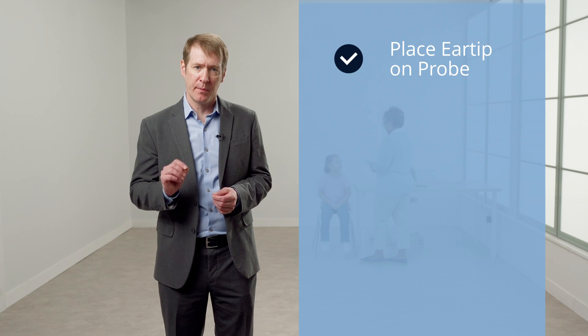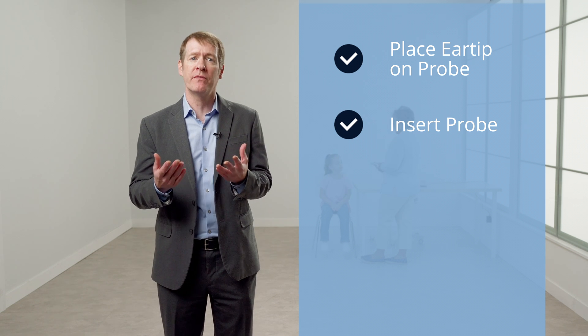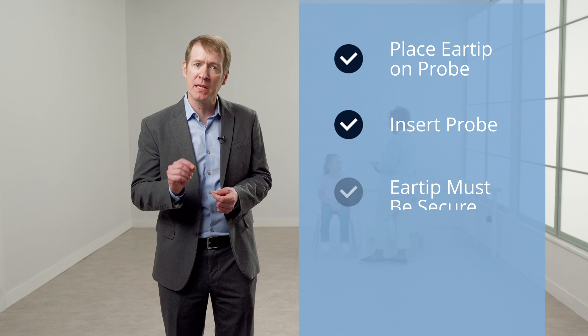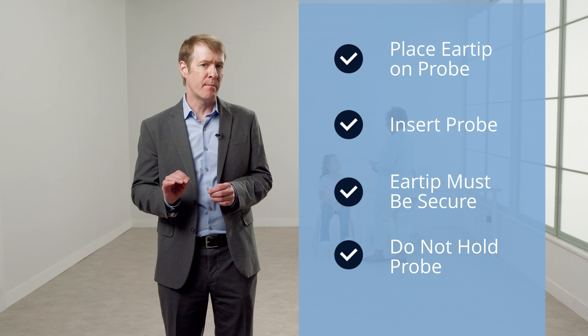For older children and adults, it's a good idea to tell them what to expect during the OAE test. You can inform them that you are going to check how their ears are working by presenting sounds to their ears with the probe, and that they just need to sit quietly for a few seconds. They do not need to pay attention to the sounds or tell you that they heard it. For all patient ages, place the ear tip firmly on the probe. Once you have inserted the probe into the patient's ear, make sure the ear tip is still firmly in place and will not easily fall out. Do not hold the OAE probe during the measurement because this can introduce noise that may interfere with the testing.